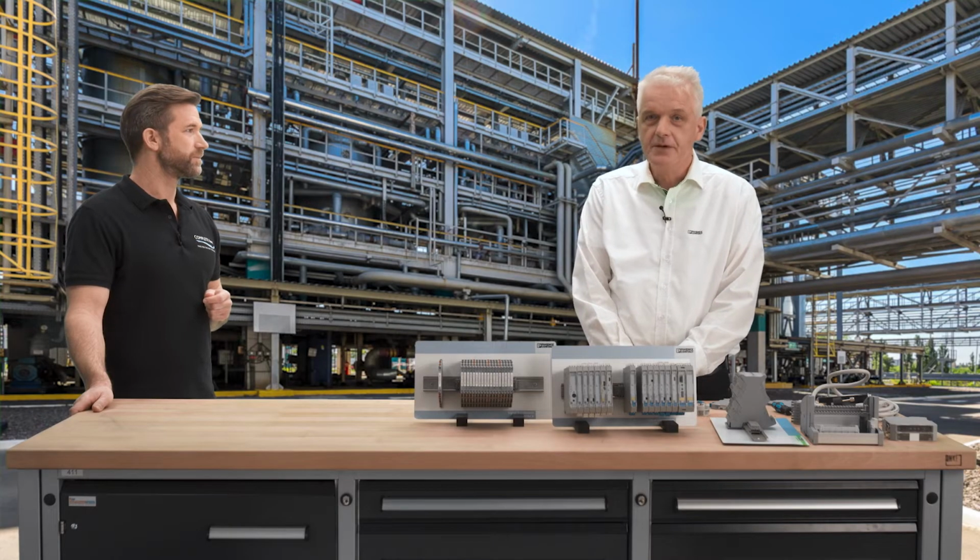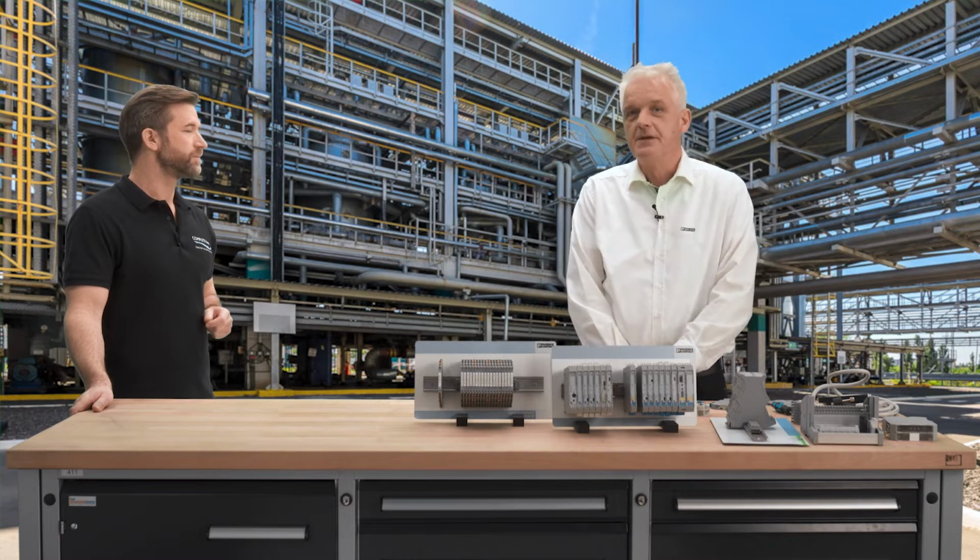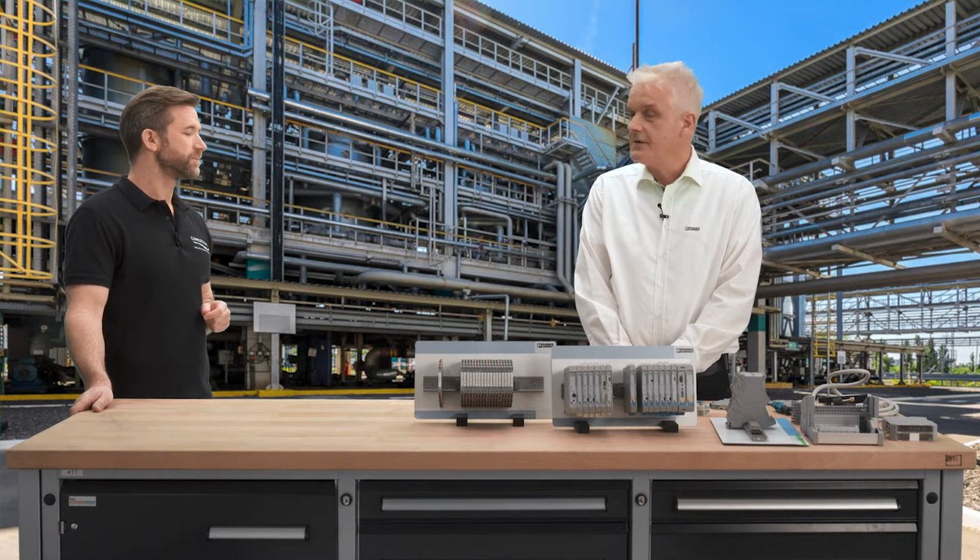signal distortions. Signal amplifying is necessary when a signal is too weak to be correctly processed by the control unit. Signal duplication is used to add a second local display or as an input to a separate process. And signal filtering: signal conditioners filter out unwanted frequencies that might negatively affect the signal chain.